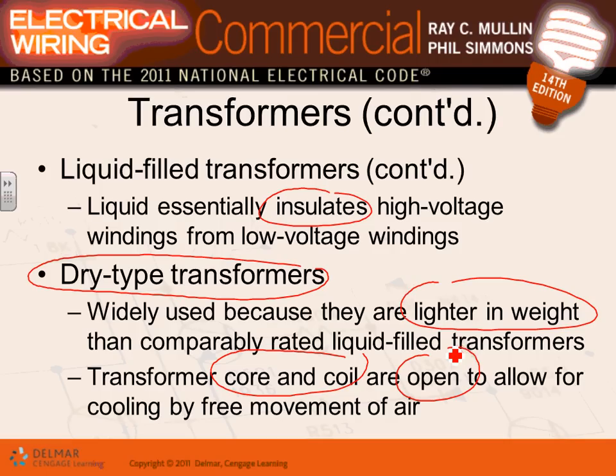So the whole idea becomes, how do you design them, if they're dry type, to dissipate the heat? You can see that they have a lot of vents on them and what's not. They design them in a way where there's a lot of exposure to the external if they are air cooled. And sometimes, in a substation, they have big fans on them. Have you seen these fan-cooled transformers? Oil fan-cooled transformers have oil and big fans blowing at them.